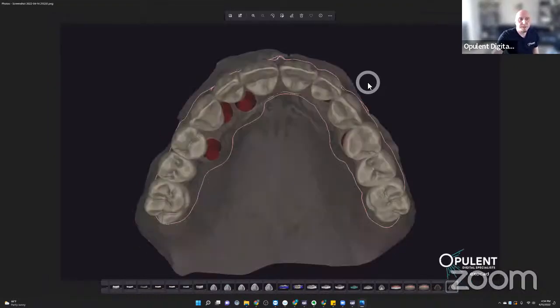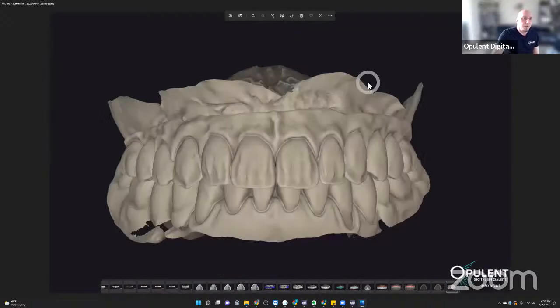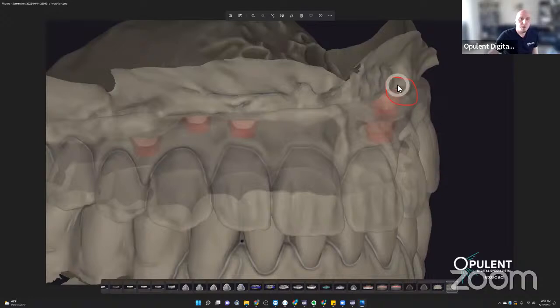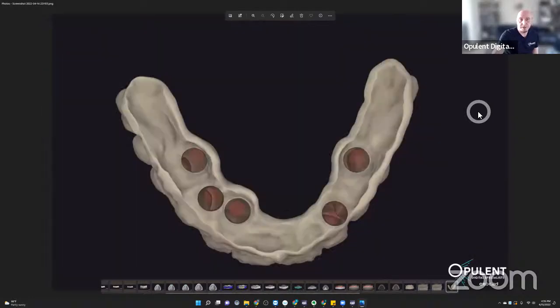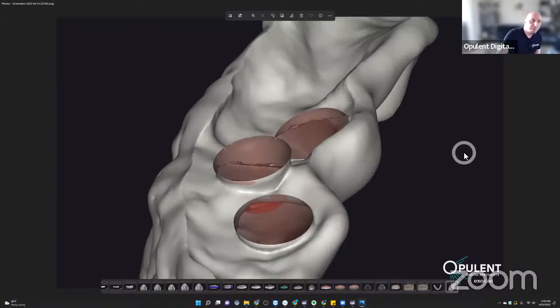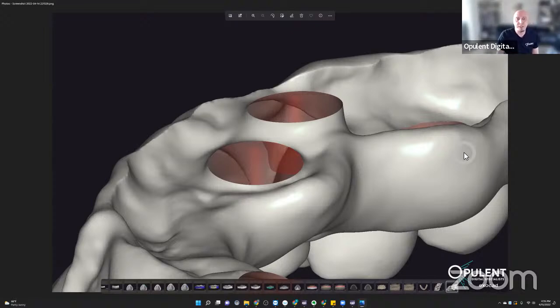We have a tissue design and ultimately we're trying to get the smallest possible footprint on the gingiva so there's no dirt or debris underneath — the patient needs to come in and get it cleaned periodically. The smaller the footprint to the tissue, the less can get trapped under there. You also have to maintain minimum thickness around your implants, otherwise the whole thing would break. It's a balancing act between the smallest footprint and sufficient thickness.